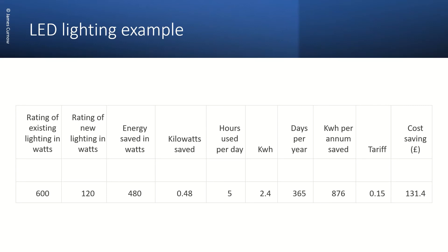So assuming that the lighting is going to be used for 5 hours per day, 365 days per year, we can calculate a saving in kilowatt hours of 876. So if we assume an energy tariff of 15 pence per kilowatt hour, this would give us a saving of £131.40 per annum.